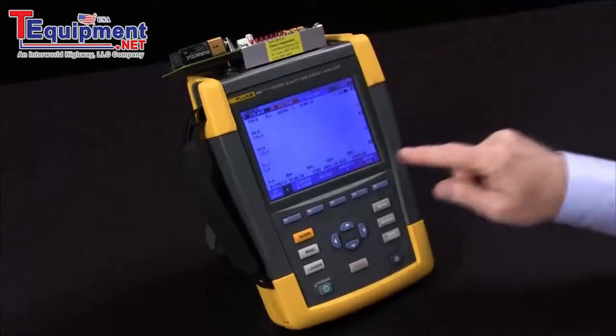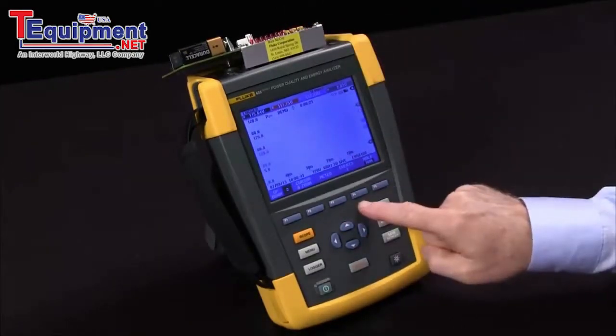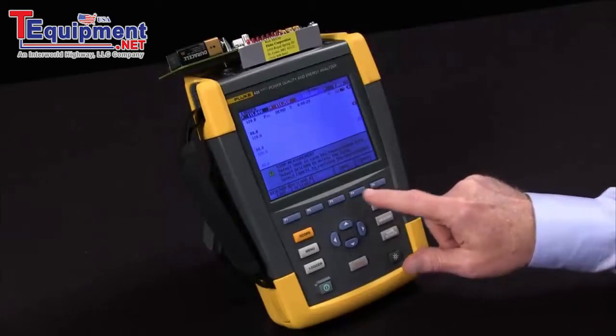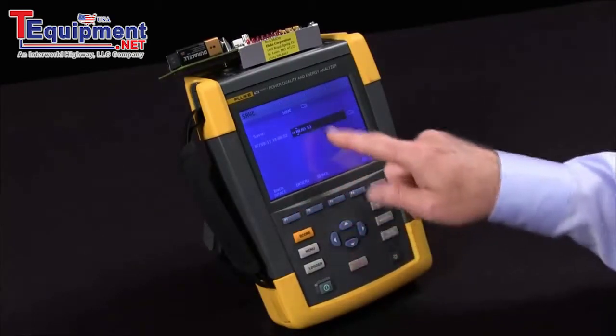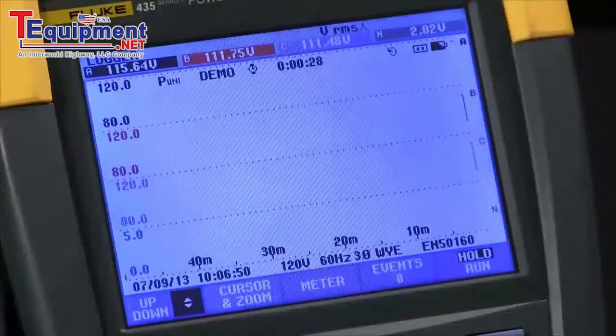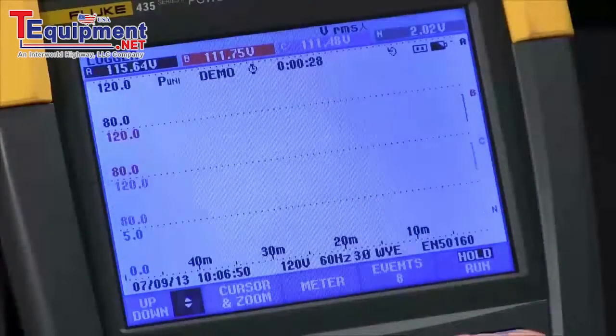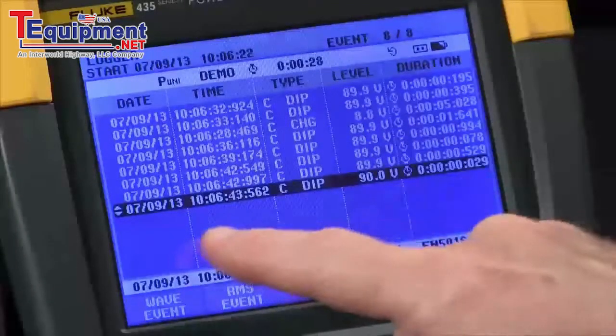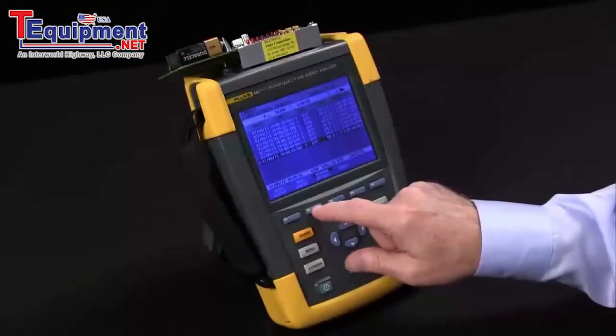We can see our trend by hitting the trend button and generate some signals. Our time base is really slow right now so we're not going to see events here, but the event counter shows we got seven events so far. I'm going to go ahead and stop the test, save the data with the factory default, hit OK, and then hit F4 to view events — you can see we captured several dips with time, date, voltage, and everything else.